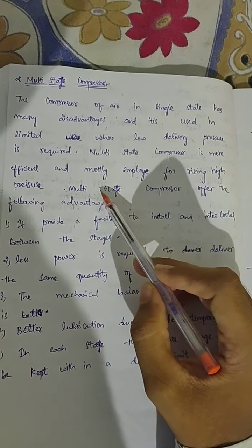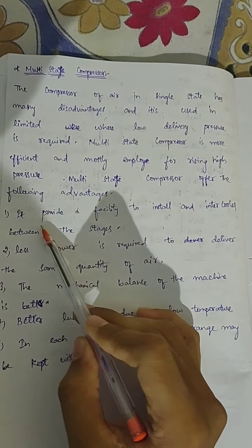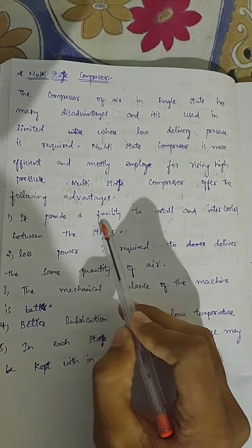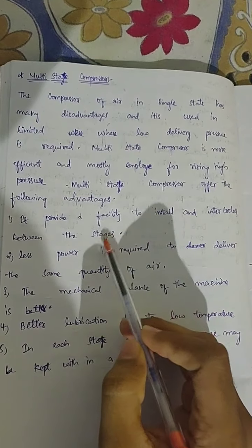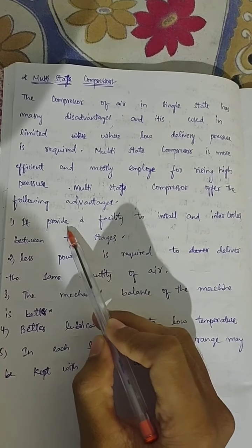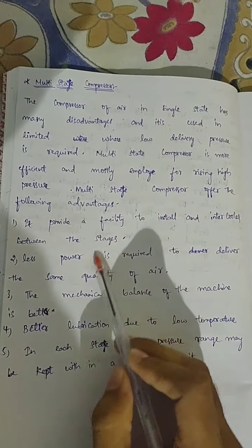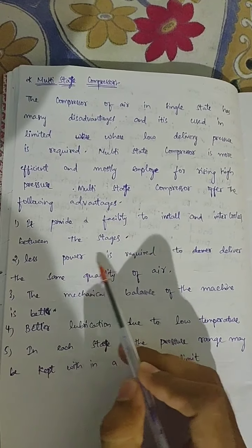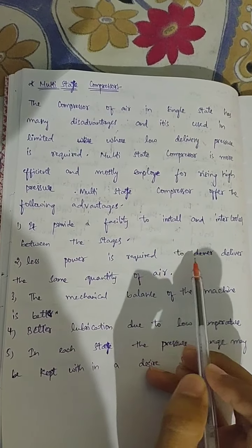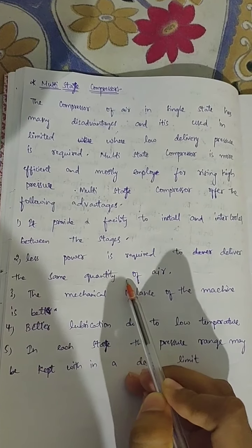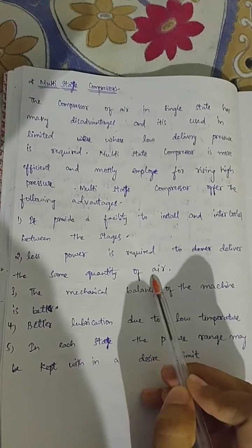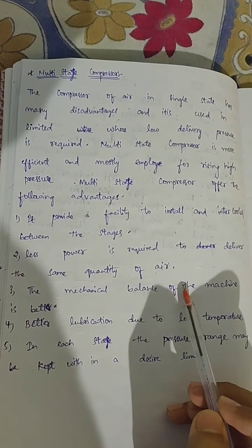The multi-stage compressor offers the following advantages. It provides a facility to install an intercooler between the stages. And the next point, less power is required to deliver the same quantity of air. And the mechanical balance of the machine is better.